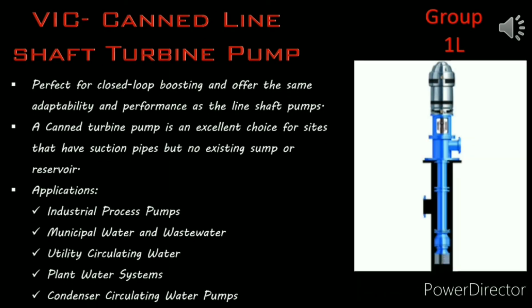Next is the VIC, can line shaft turbine pumps. Multi-stage can vertical turbine pumps are perfect for closed-loop boosting and offer the same adaptability and performance as line shaft pumps. These are short set line shaft pumps with suction pipe work linked to a can or sleeve inlet, allowing the pump reservoir to be created by the can. A can turbine pump is an excellent choice for sites that have suction pipes but no existing sump or reservoir.